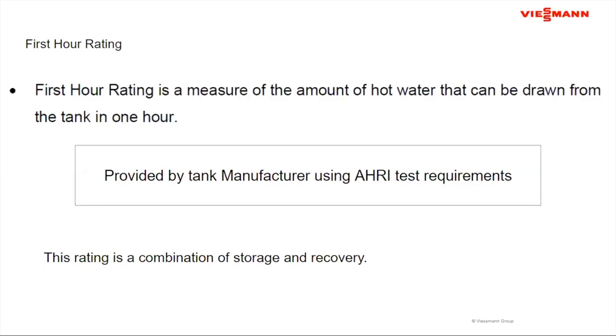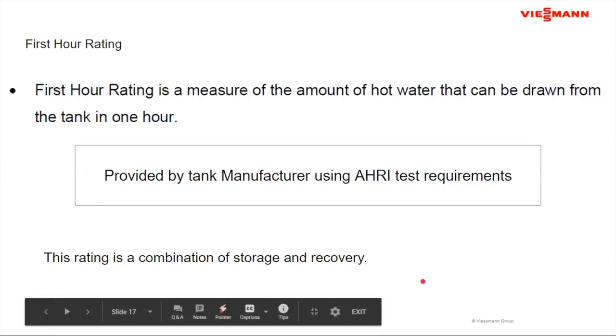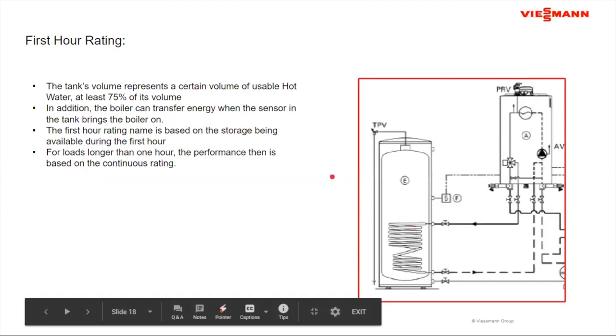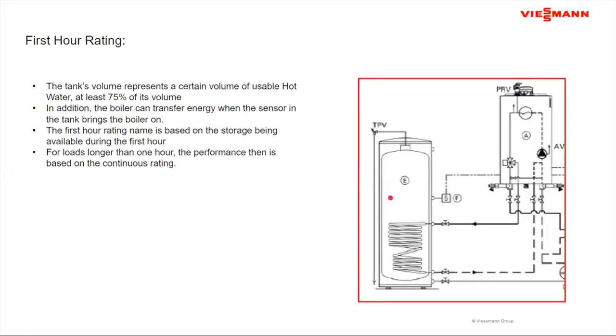First hour ratings are for storage type water heaters, indirect and direct fire. So it's a tank rating. It's a combination of recovery and storage, and it is done under an AHRI testing protocol. And again, it's a rating of storage and recovery. Where that first hour comes from is the idea that if I have a tank, in that tank I have a certain volume of water. Because of the way the water comes into the tank and there's a little bit of mixing, generally I can use about 75% of that tank's volume as usable hot water, and that's a generic number, not product specific.